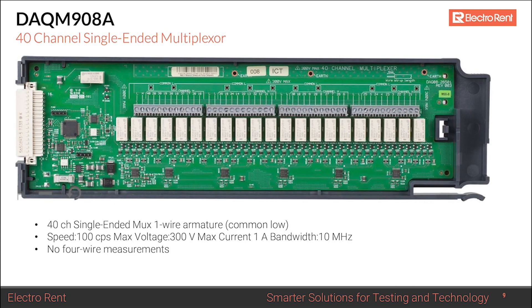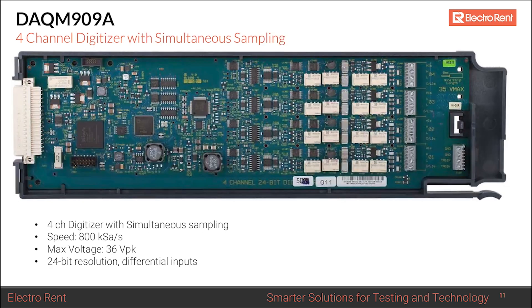The DAQM908A is a 40-channel unit — much denser and more channels per slot. However, all channels share a common low, making it single-wire switching only. This makes it ideal for signals on a unit under test that are all referenced to the same ground, such as 5V, 10V, or 12V test points. There are no four-wire measurements, no reference junction, and therefore no thermocouple measurement capability.